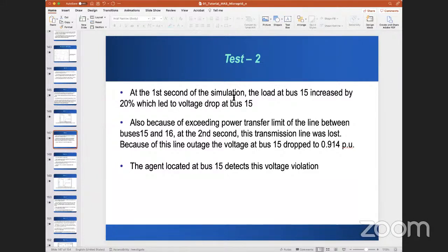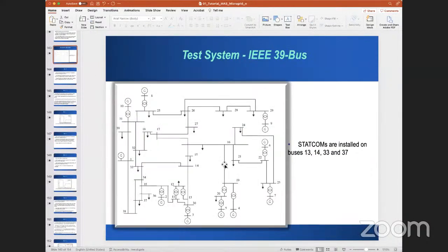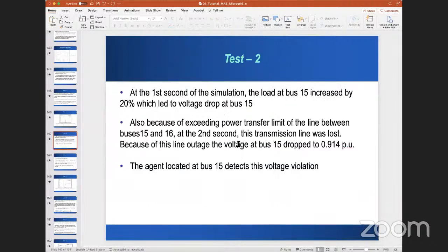At 1 second of this simulation, the load at bus 15 increased by 20%, which led to a voltage drop at bus 15, okay? Also, because of exceeding the power transfer limit of the line between 15 and 16, at the second, this transmission line was lost. Let's see, 15 and 16 is still the same line. Second scenario, same line.